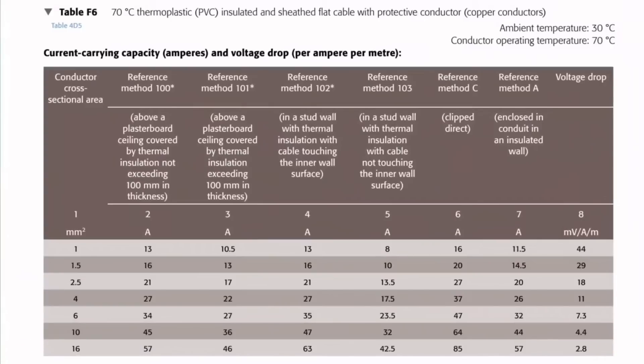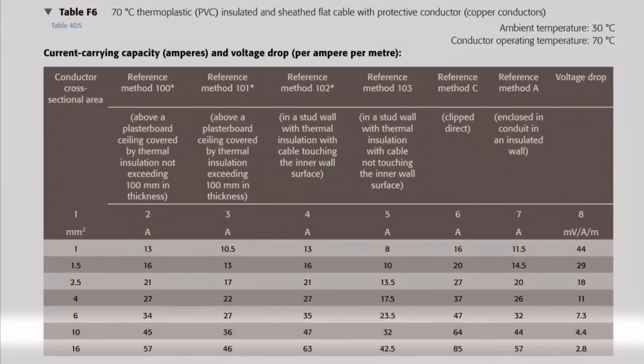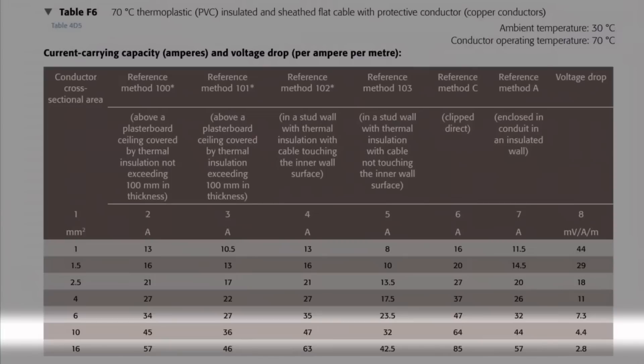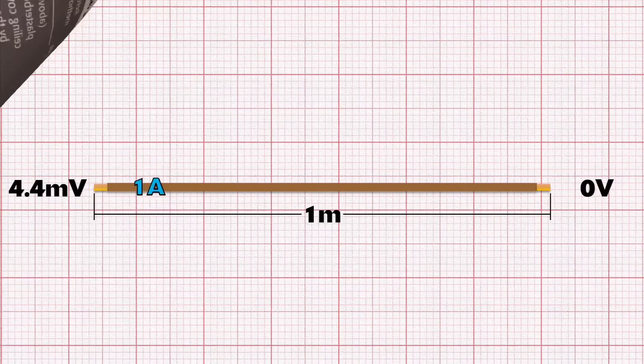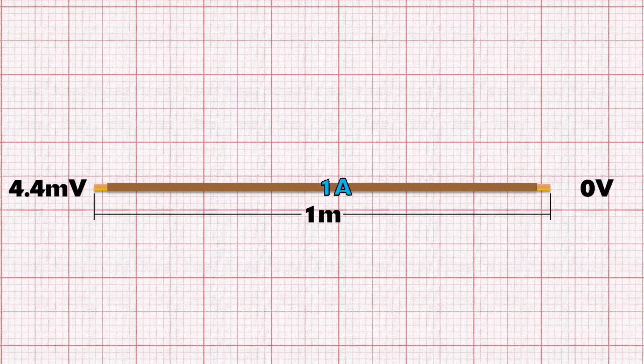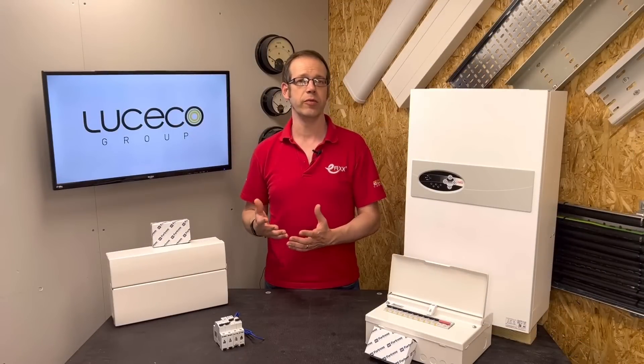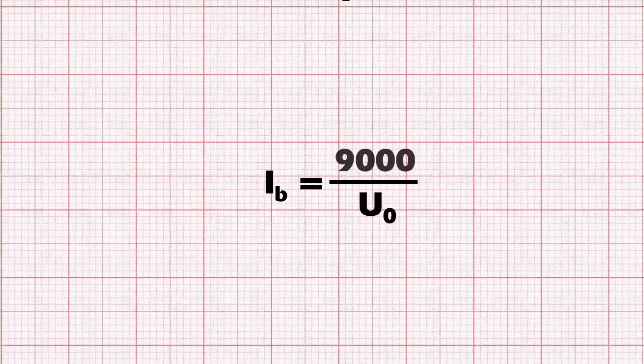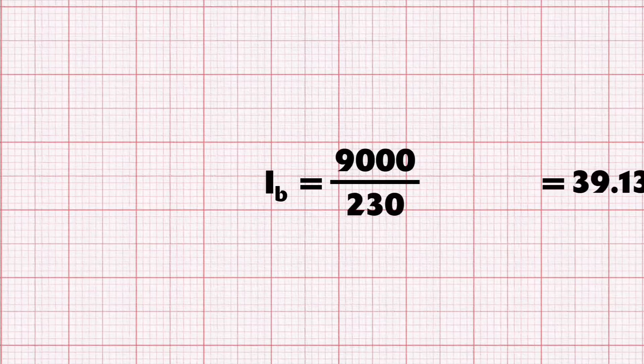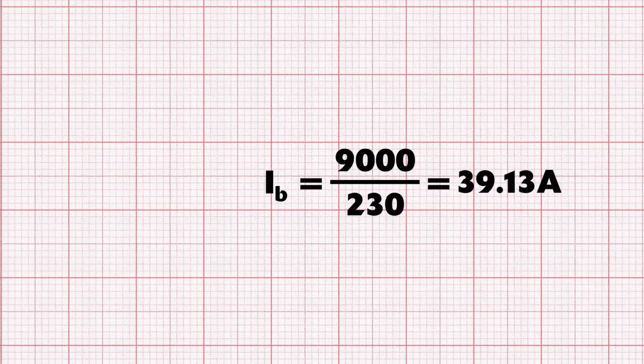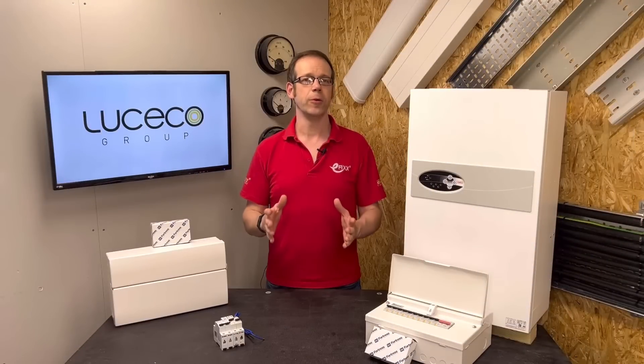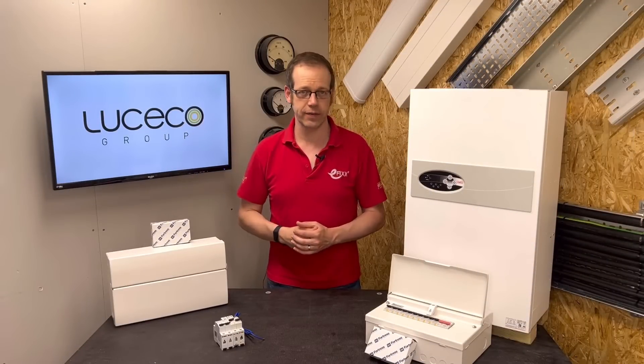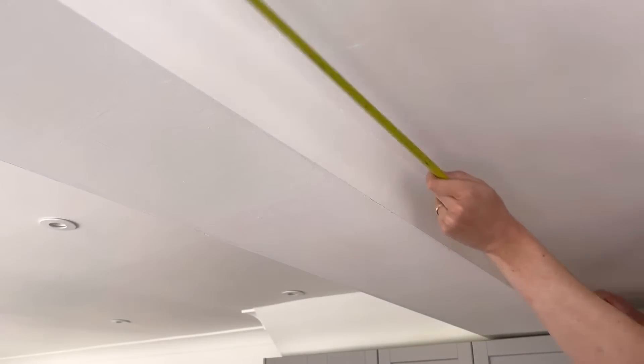Looking at the cable we selected — 10mm² — we find a value in column 8 of 4.4 millivolts per amp per metre. But our circuit is longer than one metre and drawing much more than one amp, so we use the real-world values of current and length for our circuit. The current is the design current of the circuit, which we calculated in video 2 of part 1 of this series — that came out at 39.13 amps. The length of the circuit is really important for this stage of the process, and you can find it by measuring the real-world route with a tape measure, which is generally the preferred method when adding a circuit to an existing installation.